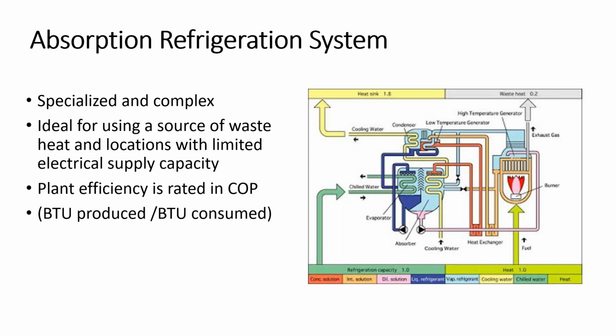So Chris, I ran across a hospital where they're talking about crystallization. I guess you need to be on top of O&M to keep these things from breaking. Right. That one I'm telling you about, the guy was telling me about the startup. They brought a guy in from New Jersey, and when they would turn the pumps on to get the flow going in the machine, it sounded like it had rocks in it, because the solution solidified at ambient temperatures, and you had to heat it up in order to get it to break down into a liquid. So when you first started the thing up, it sounds like you're pumping boulders inside there. And he thought there was something going wrong with it. The guy just said, no, that's normal.